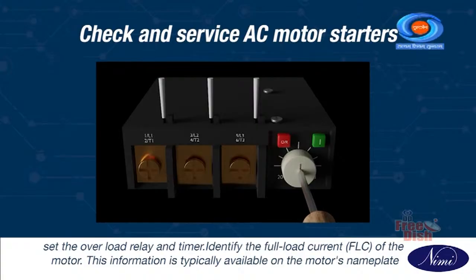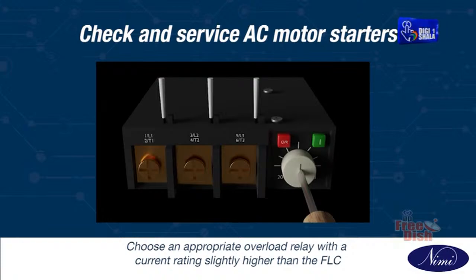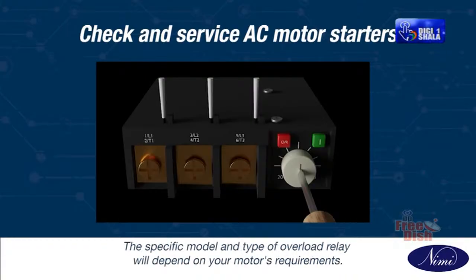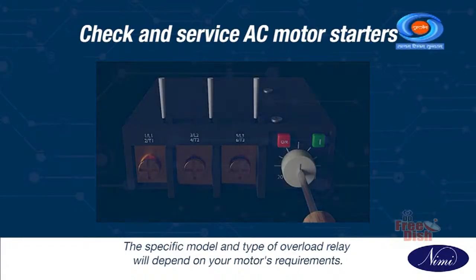This information is typically available on the motor's nameplate. Choose an appropriate overload relay with a current rating slightly higher than the FLC. The specific model and type of overload relay will depend on your motor's requirements.